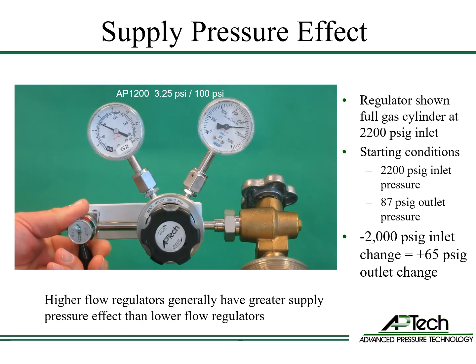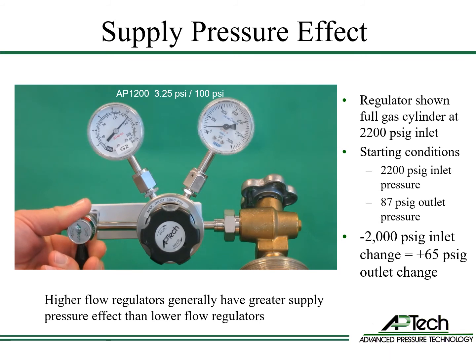Now let's look at supply pressure effect in an AP1200 regulator. In this example, the inlet pressure is 2200 psi and the outlet pressure is 87 psi. As the inlet pressure drops to 200 psi — the pressure when cylinders are often changed — the outlet pressure continues to rise. The 2000 psi drop in inlet pressure causes a 65 psi increase in outlet pressure. The AP1200 supply pressure effect is 3.25 psi per 100 psi.